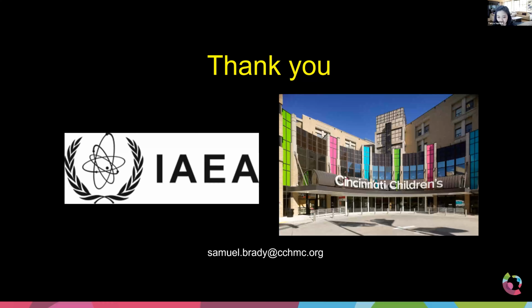Yeah. So most of that, unless you're using a GE scanner, you don't have to worry about molybdenum and rhodium anymore. Every scanner, the Siemens, the Philips, the Sectra, Hologic, they're all using tungsten now. And that's because, and I assume this is probably the same for Thailand, most institutions are moving towards tomo. Almost all systems are tomo capable.